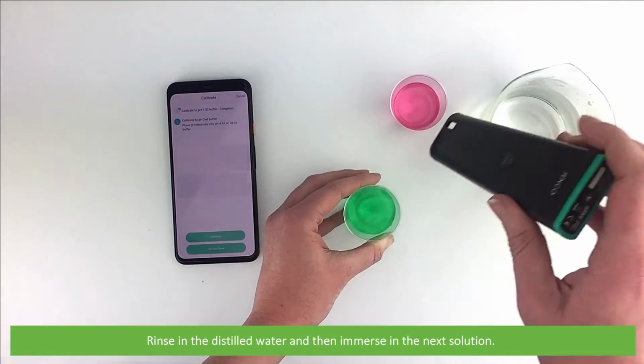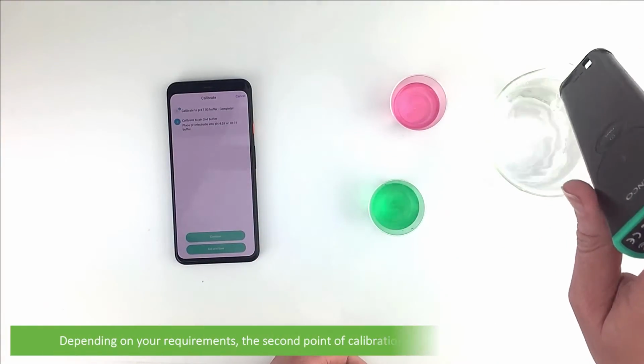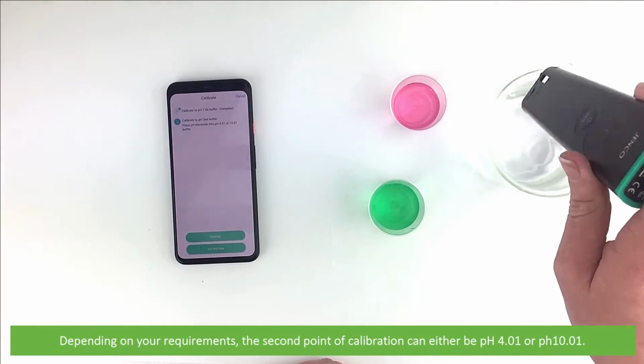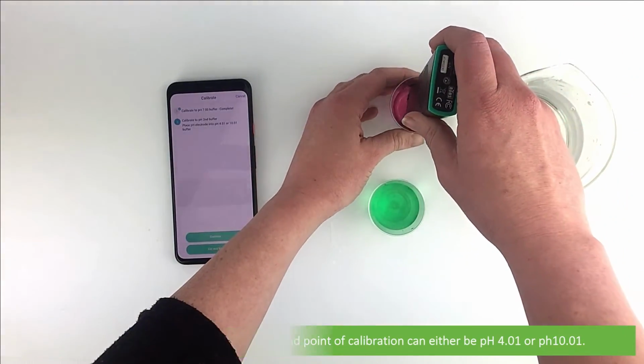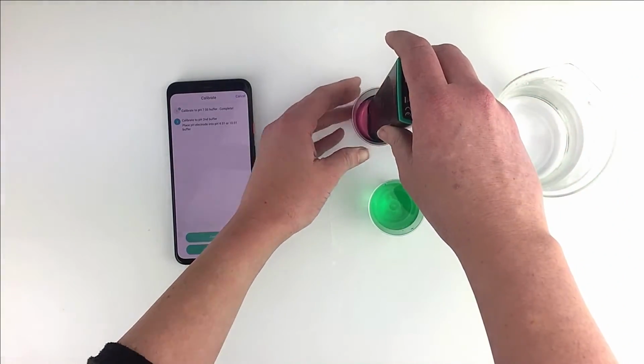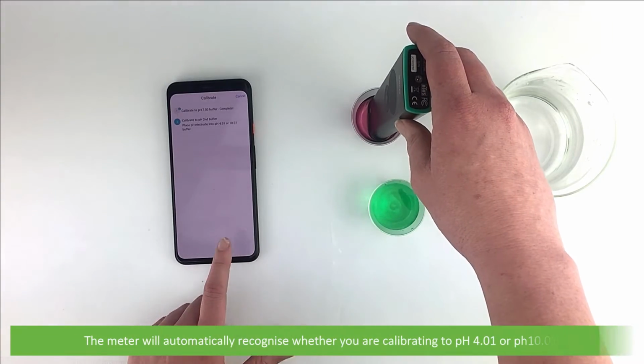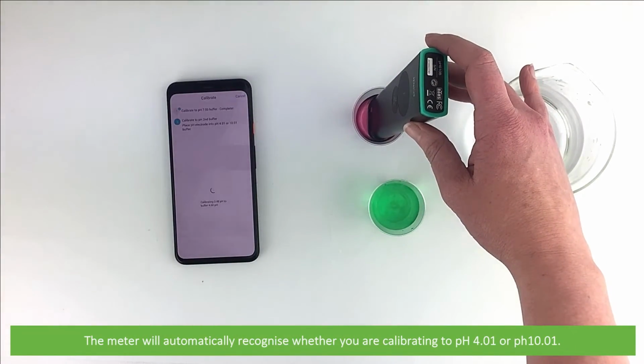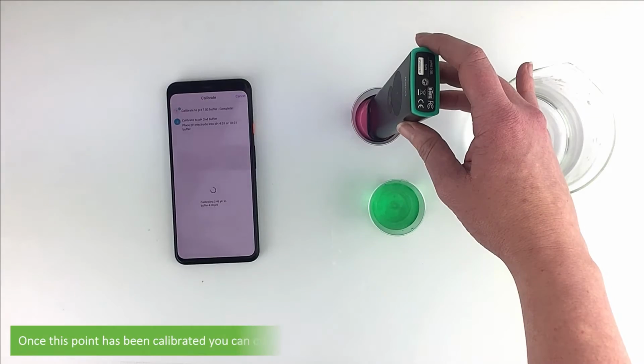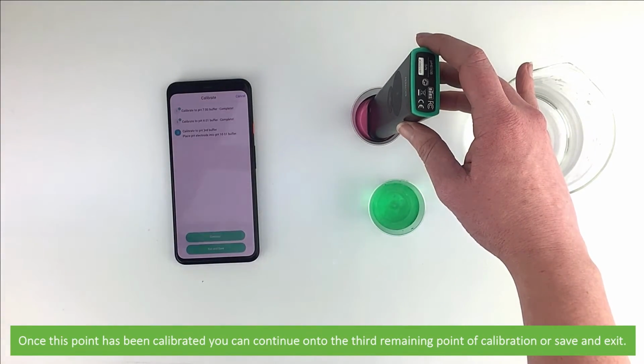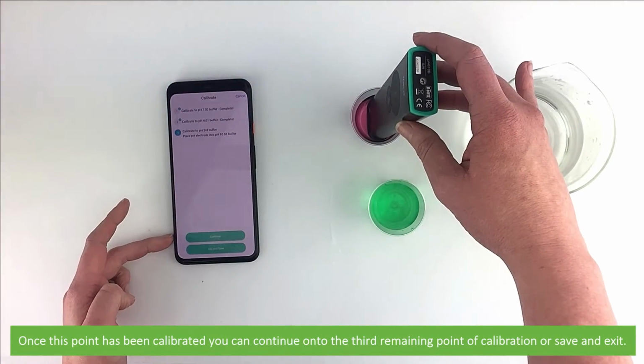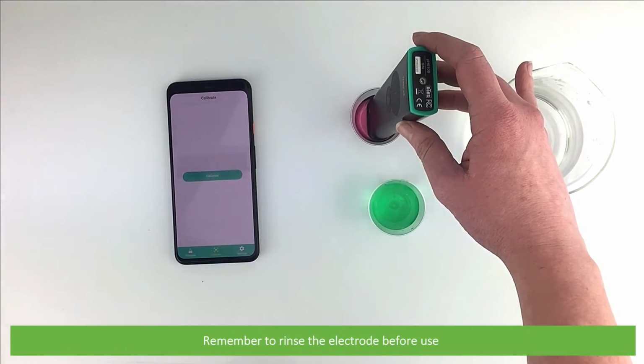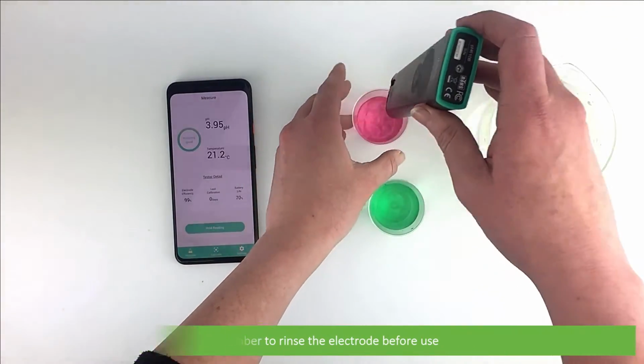Rinse the meter in distilled water, then immerse in the next solution. Depending on your requirements, the second point of calibration could be either 4.01 or 10.01. Press continue. The meter will automatically recognize whether you are calibrating to pH 4 or pH 10. Once this point has been calibrated, you can continue on to the third remaining point of calibration or press save and exit. Remember to rinse the electrode thoroughly before use.